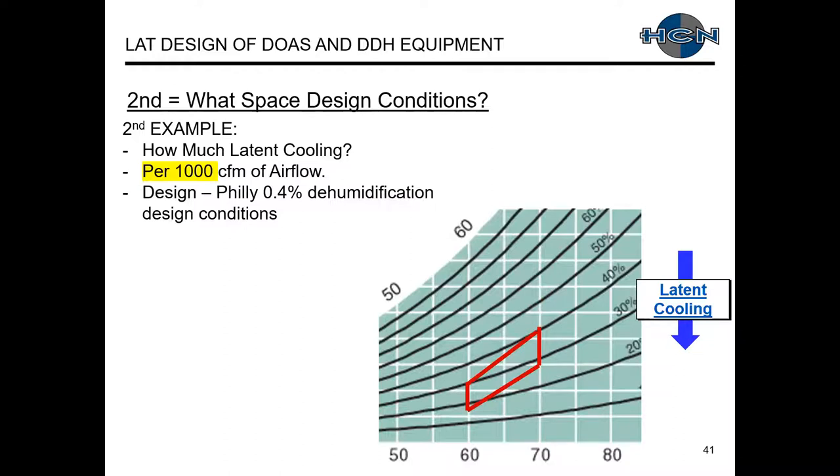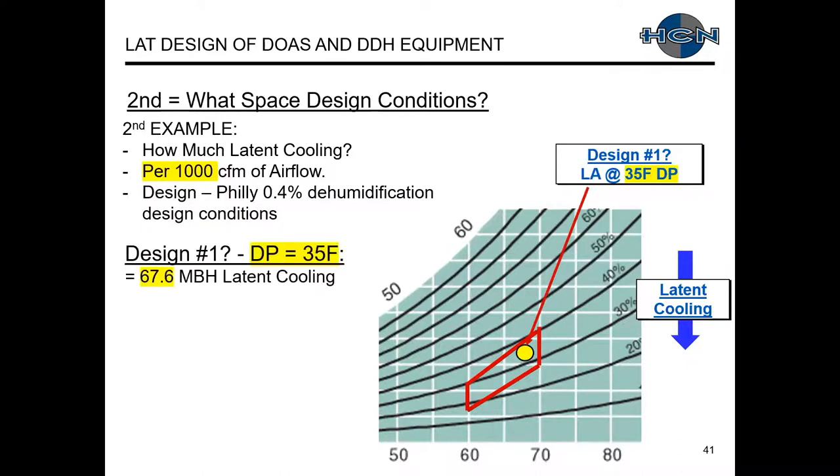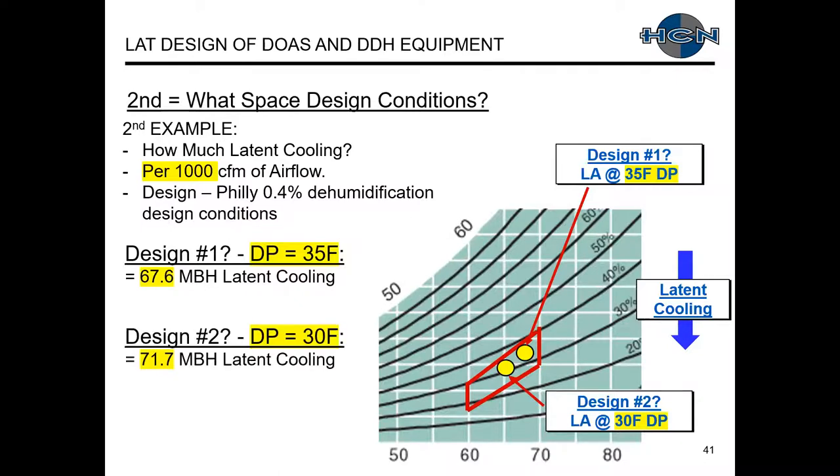For what space conditions, as an example of how much latent cooling using 1,000 CFM and Philadelphia dehumidification design conditions: Design one with a leaving air dew point of 35°F requires a certain latent cooling load. A leaving air dew point of 30°F requires a slightly higher capacity. There's not a large difference between the two conditions, but any 5–10% difference could be meaningful as an additional factor in your design input conditions.